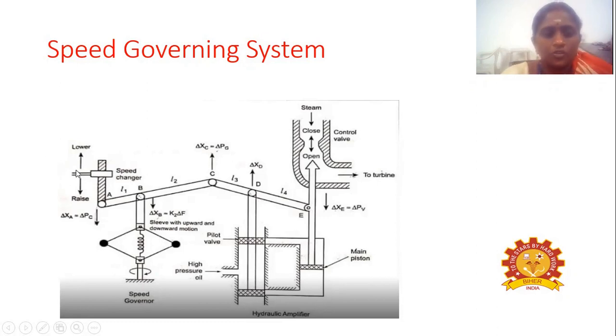If you want to lower the speed, you have to pull the knob in the upward direction. When it moves upward, point A also moves upward. Then points B and C move downwards, then point D moves downwards, which means the high pressure oil is unable to enter the hydraulic amplifier. When point D moves downwards, point E automatically moves in the upward direction. So it closes the steam path, and the amount of steam entering the turbine is reduced. Like that, we can maintain the speed. That is the speed governing mechanism, by which we can control the speed of the alternators.